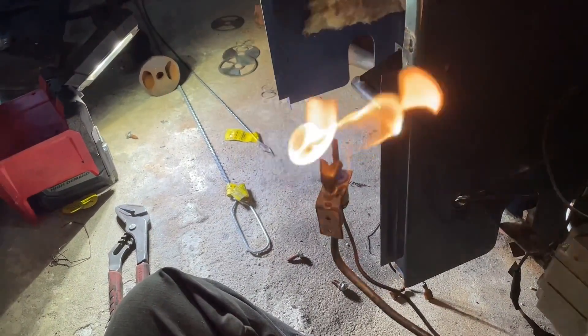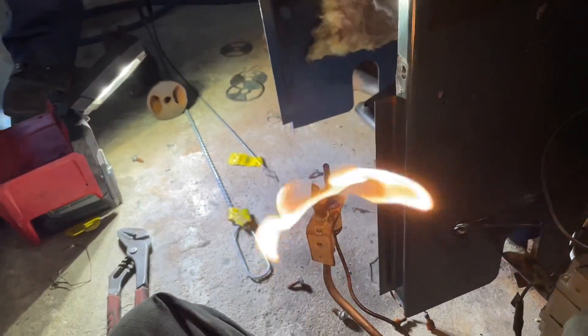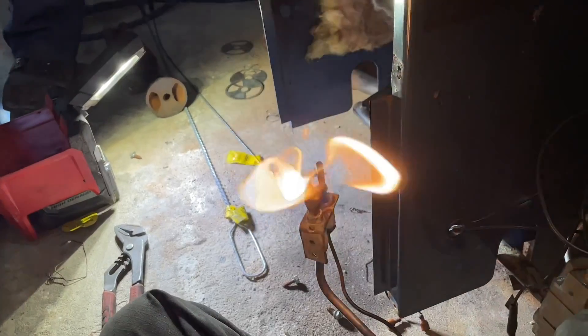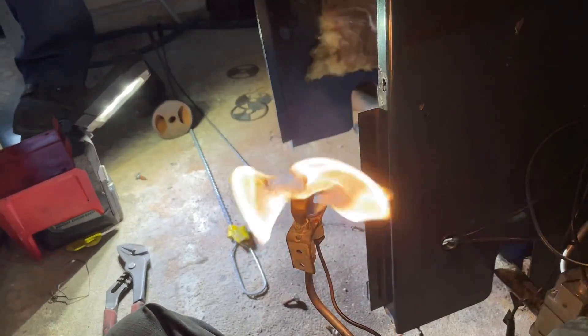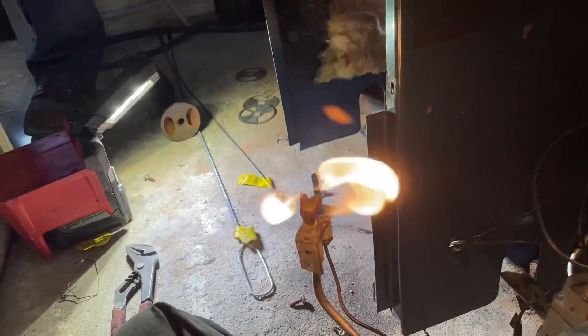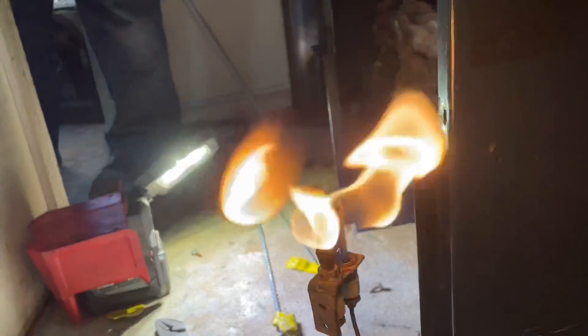I had Kelvin grab me a lighter because I'm going to replace the pilot tubing and pilot assembly and the thermocouple anyway — but there's your culprit. This is why the boiler carbonized. If you've got a pilot flame the size of the Statue of Liberty's torch, you've got big problems. Look at that — it's crazy.